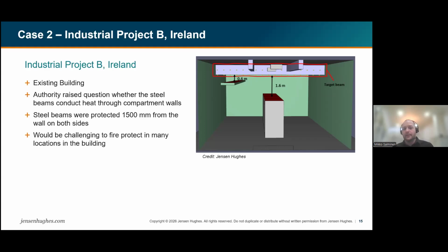And the steel beams were protected 1,500 millimeters from the wall on both sides. I think that's based on some regulation in Ireland, but it would have been challenging to fire protect it more or box it out some way. So we investigated the existing situation and wanted to check if this design can achieve the compartmentation criteria.